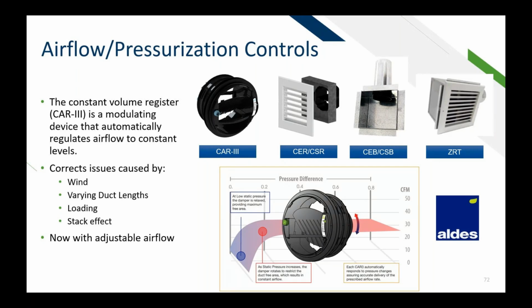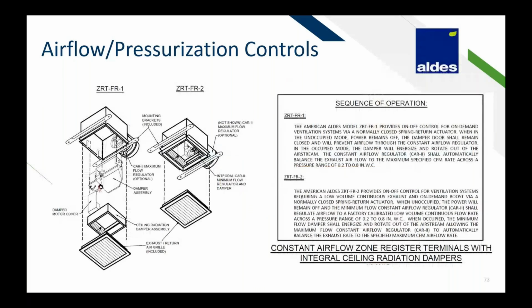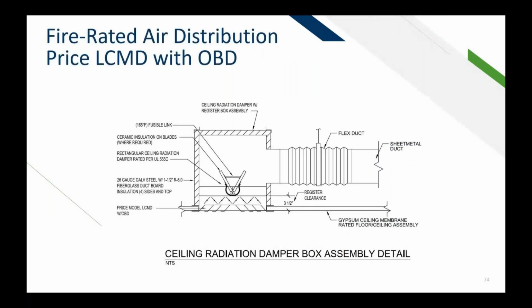So that can be dropped into a register, a boot, or even a zoned register terminal. A zoned register terminal is a device where you flip a switch and a flap closes. You flip a switch down, the flap closes onto that circle right there, where the constant airflow regulator is in the collar. Now, if it's a ZRT2, on that flap is another constant airflow regulator, so when you close it, it goes to minimum flow. So you can go between minimum and maximum flow, or shut off to maximum flow. Note that this can also be a fire rated assembly. It can be with or without fire rating, and it's a pretty good little device for some demand control ventilation.